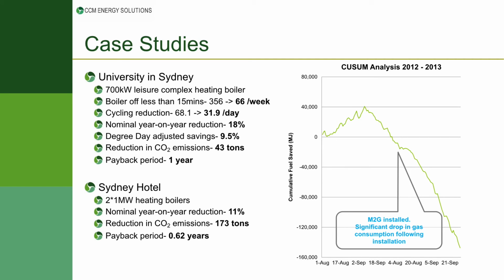To just finish, a couple of very quick case studies. A university in Sydney that we worked with, a 700 kilowatt leisure center heating boiler. The important value here is that the fuel reduction was 18%. When we did our regression analysis and degree day adjustments, we were down to 9.5%. Payback period was under 1 year, with 43 tons of CO2 reduced. You can see here the cycling reduced from about 70 times per day down to about 30 times. Not only do you get the energy savings, but there's less wear on the burner, which means you get prolonged life out of the system.